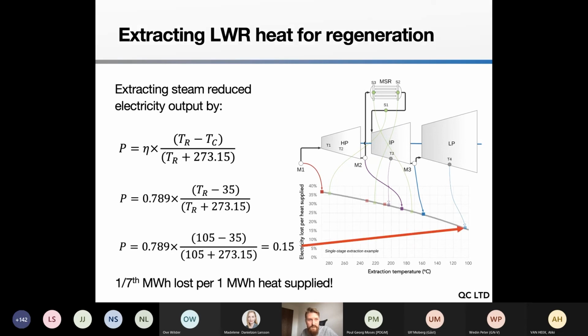So for instance, if we want to heat a direct air capture sorbent to 100 degrees Celsius or so, a nice thing would be to use, at least in the Arabelle steam cycle, the T4 port in the low pressure turbine, which is at 105 degrees Celsius steam. And if we plug that in, we lose... So that steam has already gone through most of the turbine cycle when it gets to that point, so it has very little energy left to give to the turbine blades and produce electricity from. So you only lose about 1/7 of a megawatt hour of electricity for every megawatt hour of heat that you could supply at that temperature to something else. So in that sense, it's a very nice way, especially when you're far down the turbine cycle here, to make use of heat.